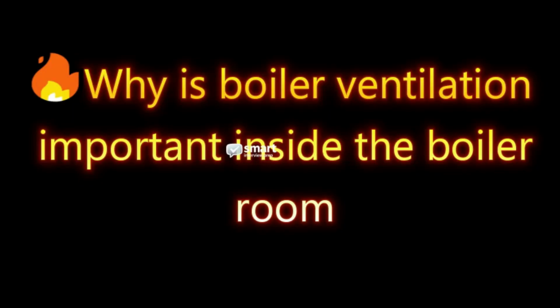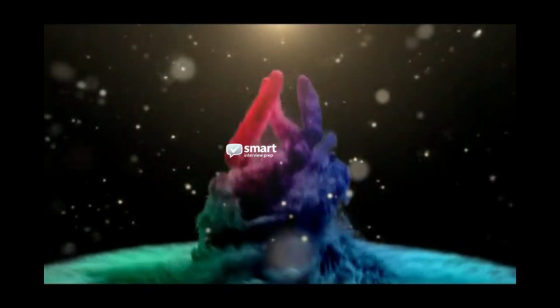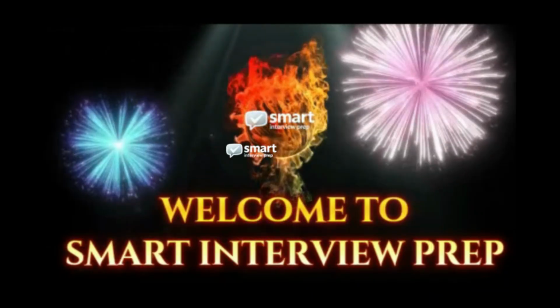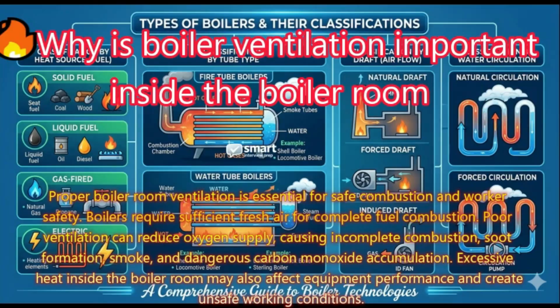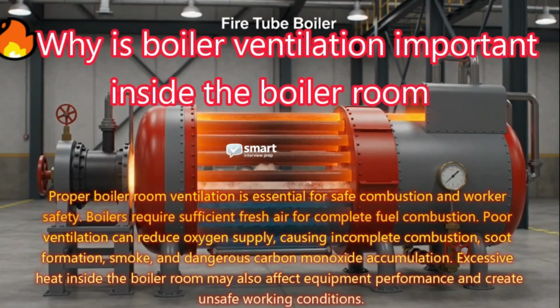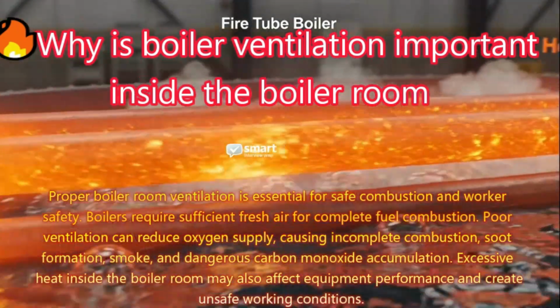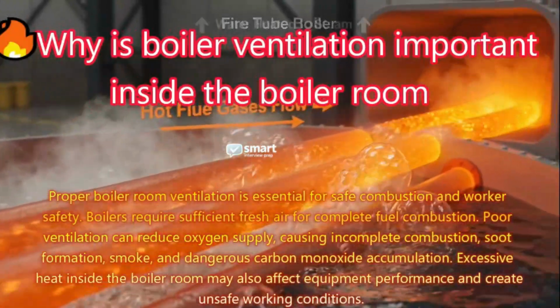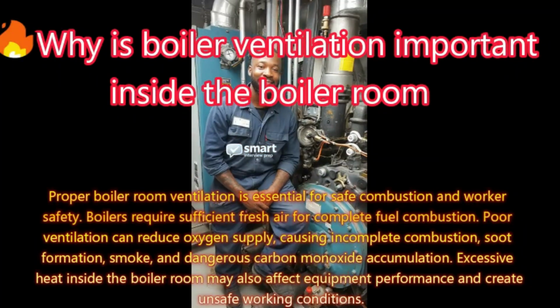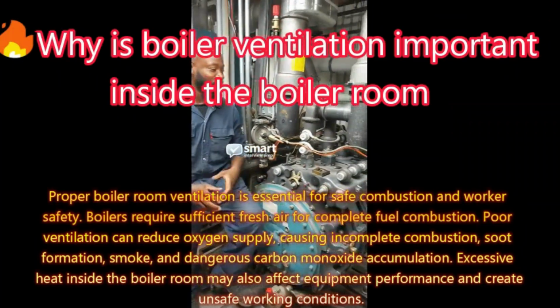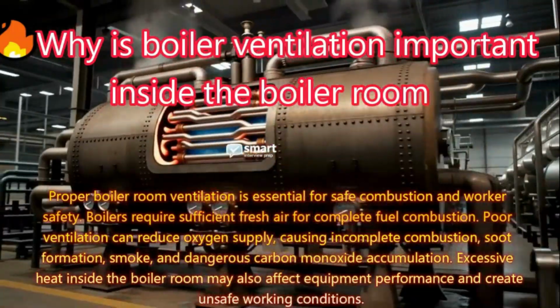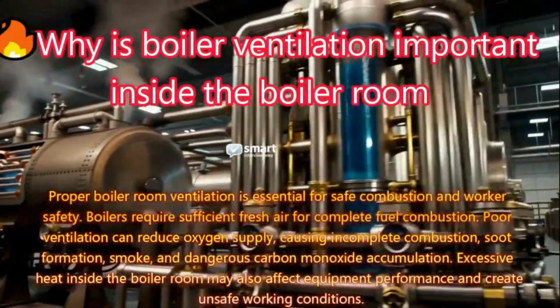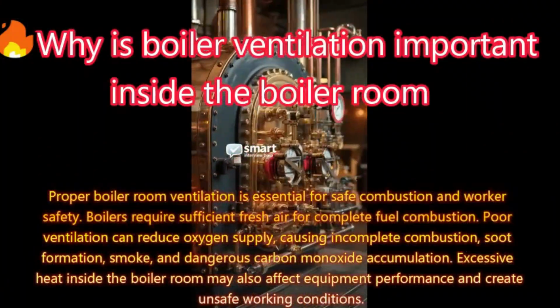Why is boiler ventilation important inside the boiler room? Answer. Proper boiler room ventilation is essential for safe combustion and worker safety. Boilers require sufficient fresh air for complete fuel combustion. Poor ventilation can reduce oxygen supply, causing incomplete combustion, soot formation, smoke, and dangerous carbon monoxide accumulation.